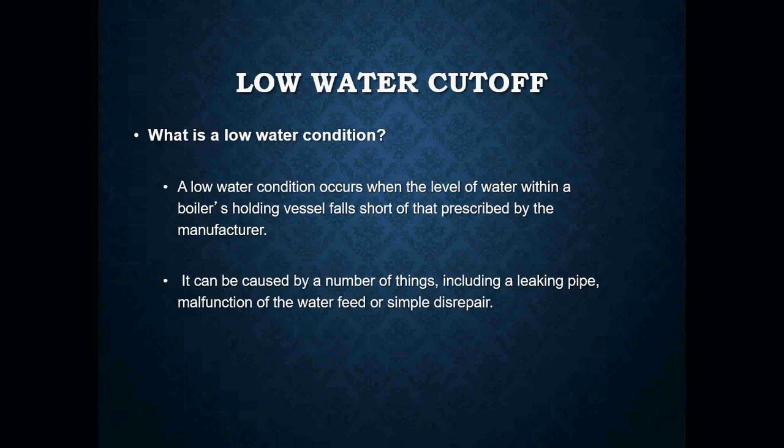Low water situations on boilers is a very serious condition. One of the biggest catastrophes a boiler mechanic can run into is a boiler running completely dry because of a malfunctioning water feed. The low water cutoff is the only device on a boiler that is going to be able to sense the water level — if it's corroded, disrepaired, broken, or miswired, that can honestly be a very dangerous situation for the mechanic, the homeowner, or business owner.